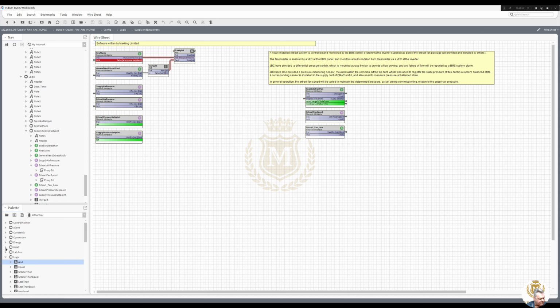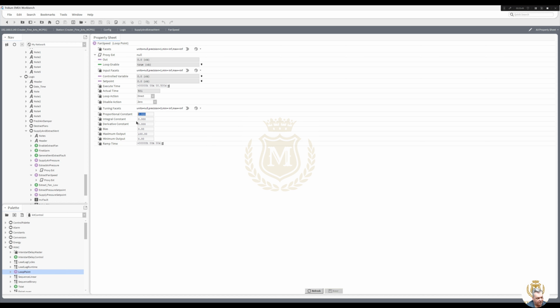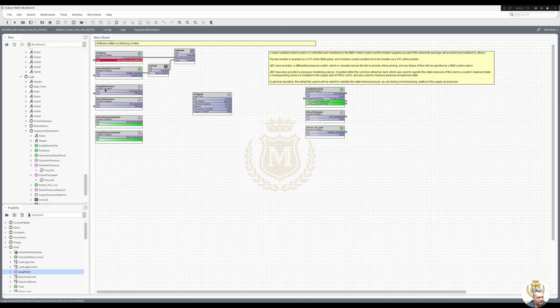For the speed, we will use a loop. Fan speed. Pin slots, set point, control variable, loop enabled. And we'll do the prop int. And we'll set a 2 in there. We'll set a 1 in there for the moment. And we go save. We've got only one fan speed, and it's extract fan speed and extract pressure there. So that's my control variable. That's my set point.